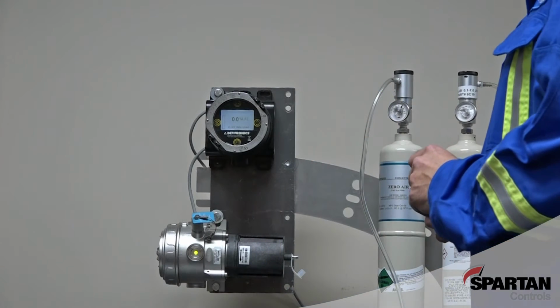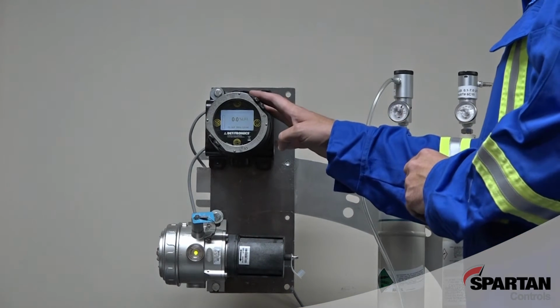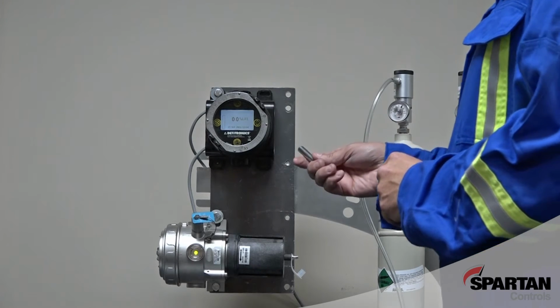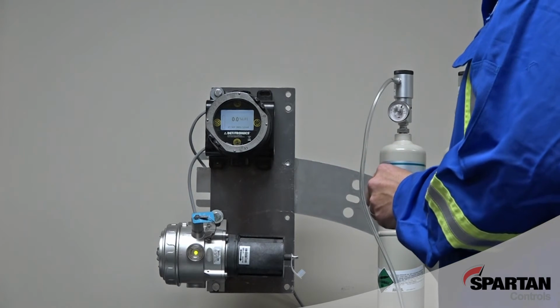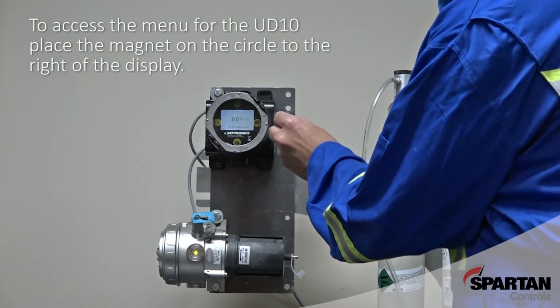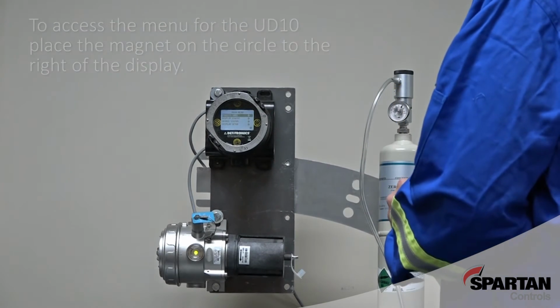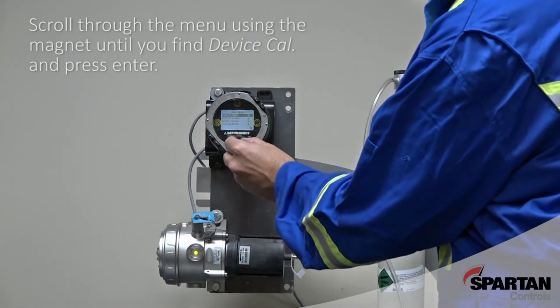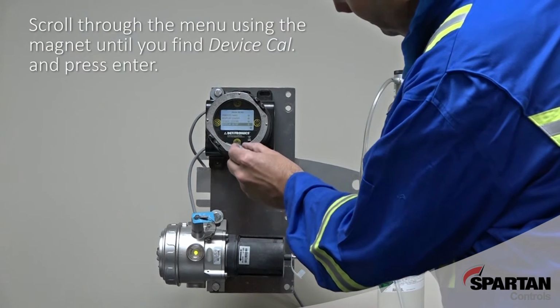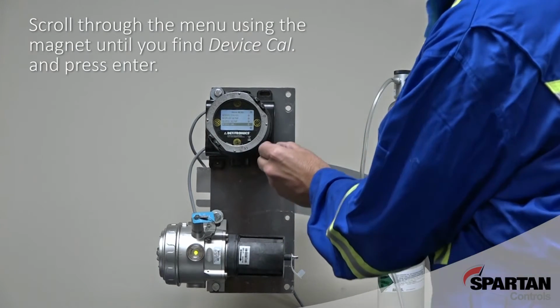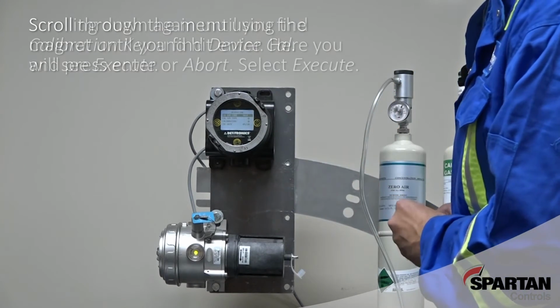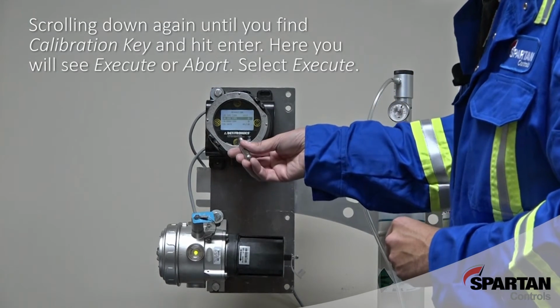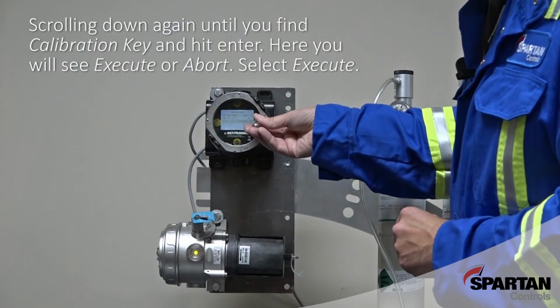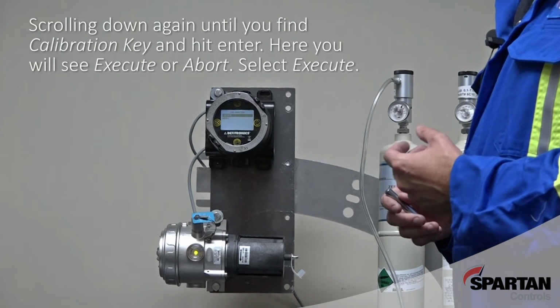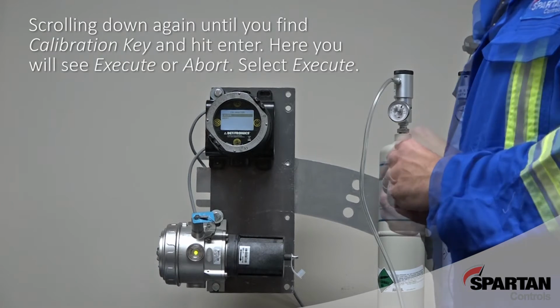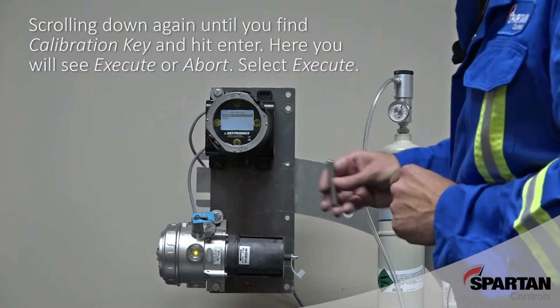To perform the calibration of this detector, I will use the UD10. Using the magnet, you can scroll through the menu of the UD10. The menu of the UD10 is initiated by placing the magnet in this position. Once you enter the menu, you can scroll down to the menu item that says Device Cal and enter. Again, scroll down to the calibration key, enter again, and you'll get a field that says execute or abort. So we can execute the calibration by keying the execute.